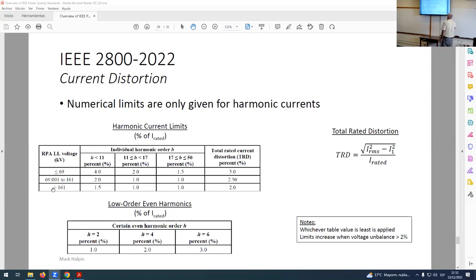Right? So, of course, this unbalanced thing is, we have an IEEE group that is working on this, but we still have a ways to go, right? And so this is a scary thing. But so far, going back to the two projects that are trying to look at the correlation between unbalance level and current emissions, it does seem that there is some linear dependence on traditional harmonic emissions based on unbalance. So it seems to make sense that if unbalance level goes up, then maybe that should go up. But it doesn't appear to be anywhere close to 100%. That seems to be much too much. But that's a work in progress.